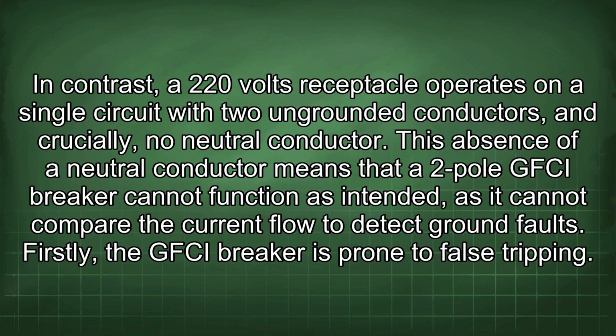In contrast, a 220 volts receptacle operates on a single circuit with two ungrounded conductors and, crucially, no neutral conductor. This absence of a neutral conductor means that a 2-pole GFCI breaker cannot function as intended, as it cannot compare the current flow to detect ground faults.